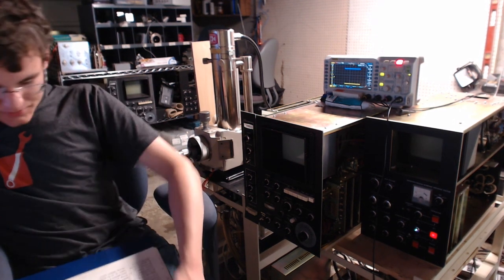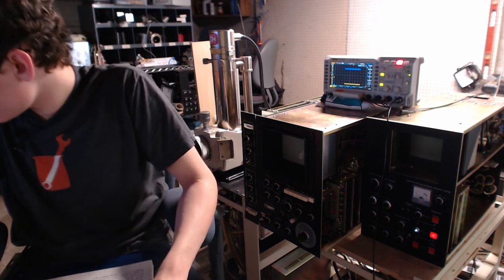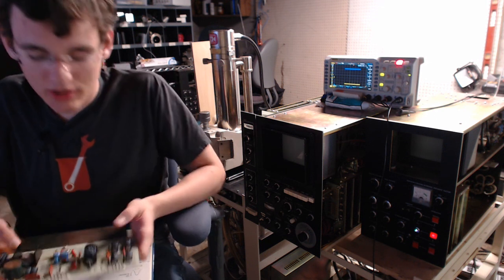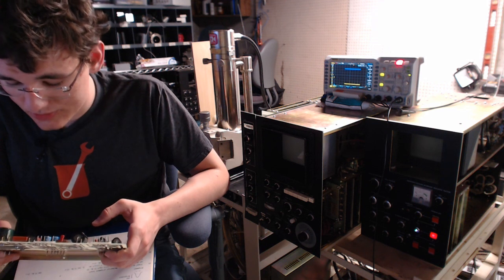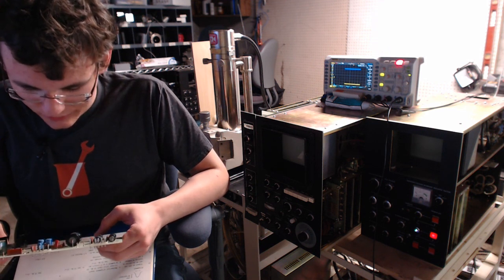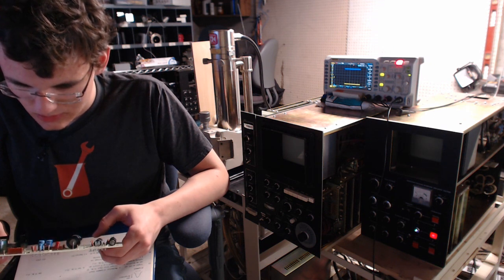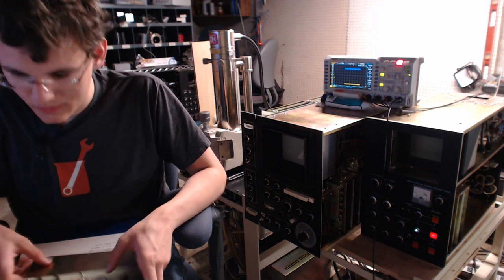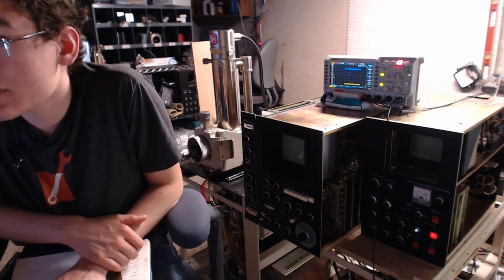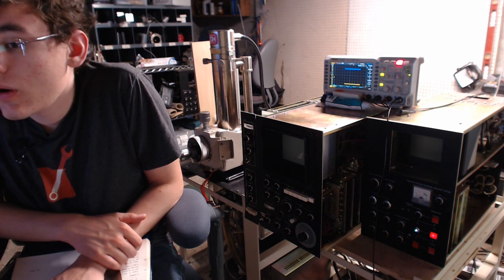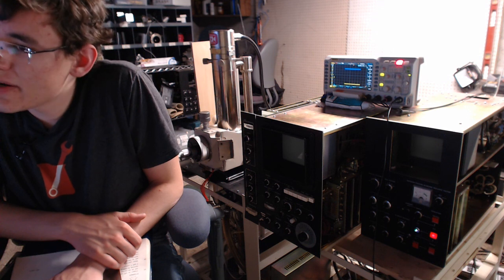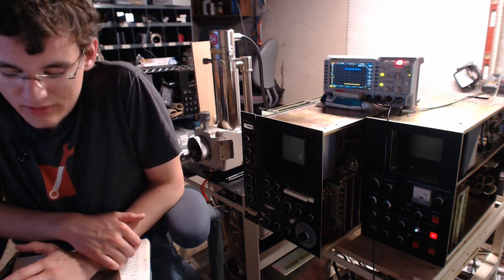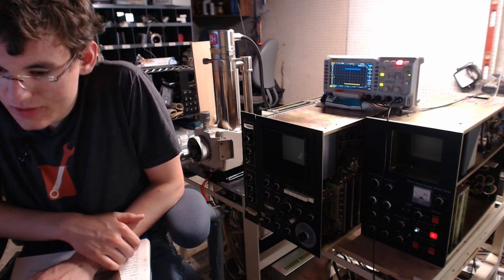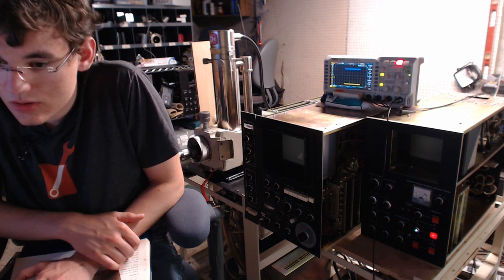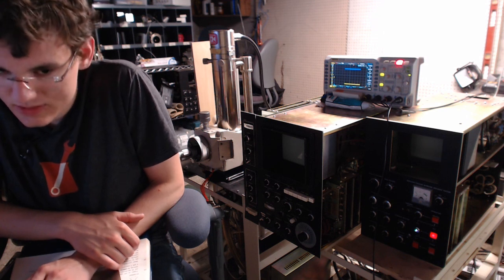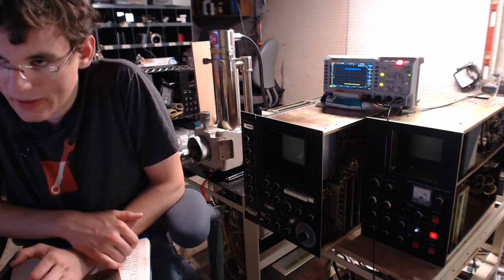No, changing the contrast control adjusts the voltage somewhere right here actually, and it changes it between -300 and -700 volts. Which is inside of the photomultiplier. But you know what? Changing the contrast only makes it more visible. It doesn't necessarily make it more likely for the noise to be there. Because the noise is there, just more visible as I increase contrast. So contrast is fine, which means the photomultiplier is fine. And because I don't get the noise when I'm in the backscatter detection range, it's not contrast. Contrast is just what makes it visible, because I'm basically making the photomultiplier more powerful by turning contrast up.